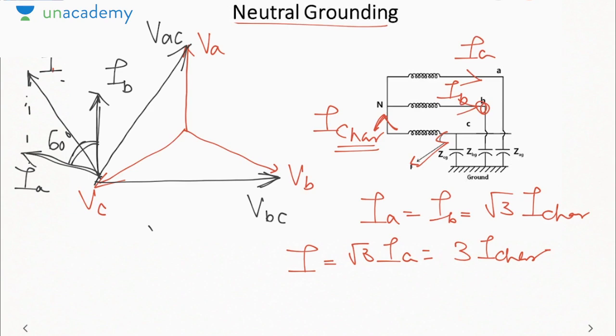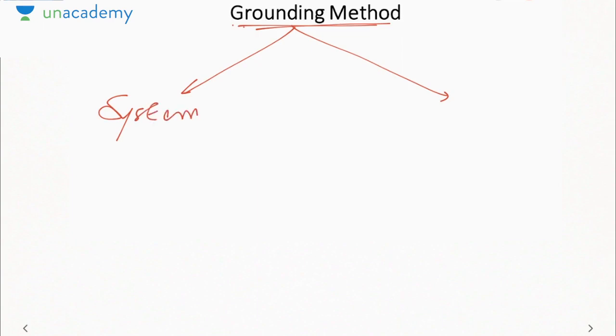Okay, and the system voltage or the phase voltage will become equal to line voltage, due to which arc will be formed. Hence we have seen the two types of disadvantages when the neutral is left ungrounded. High line charging current flows and the system voltage becomes dangerously high. So let us discuss how we can ground the system. So grounding methods are basically divided into two parts. One is called system grounding, the other is called neutral grounding.